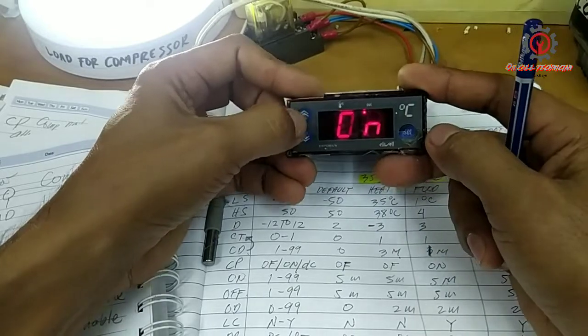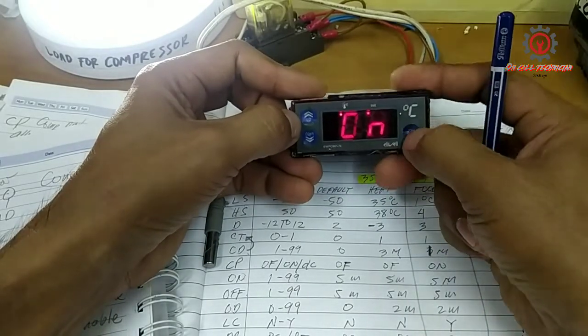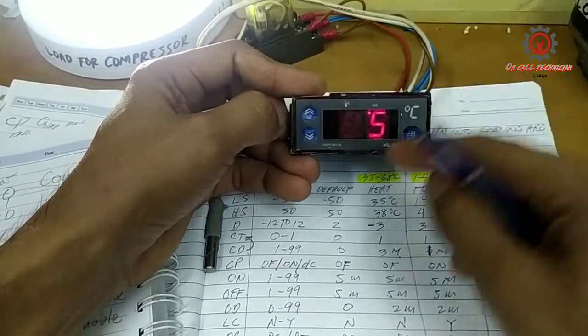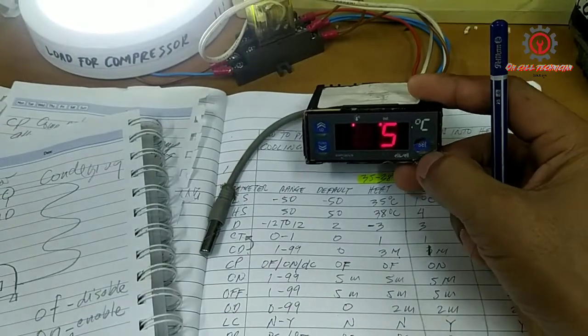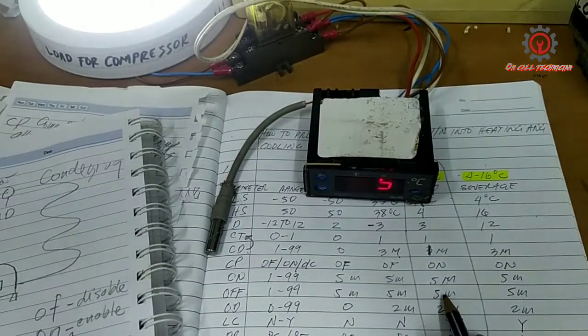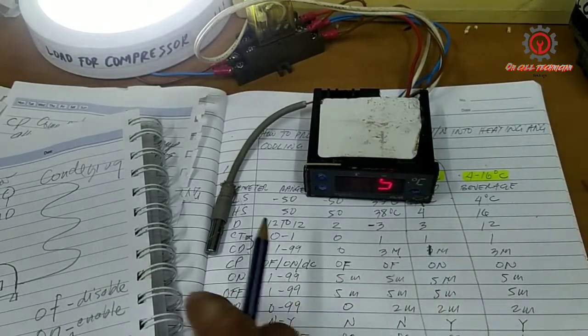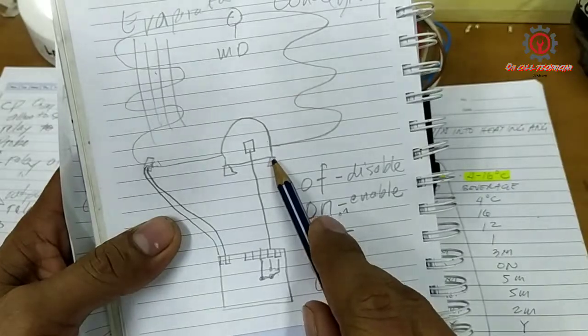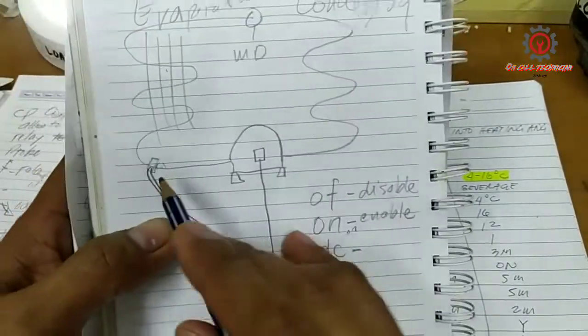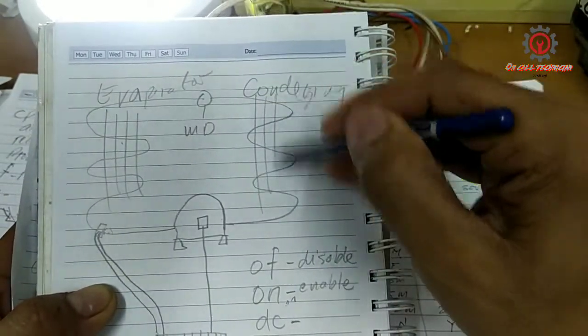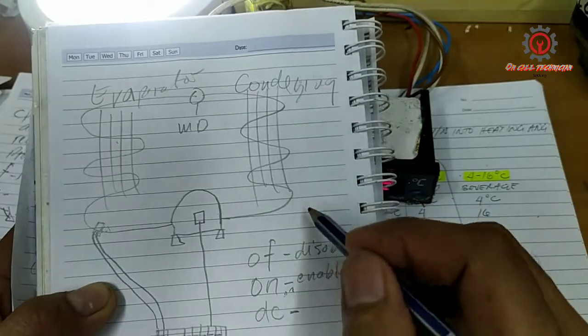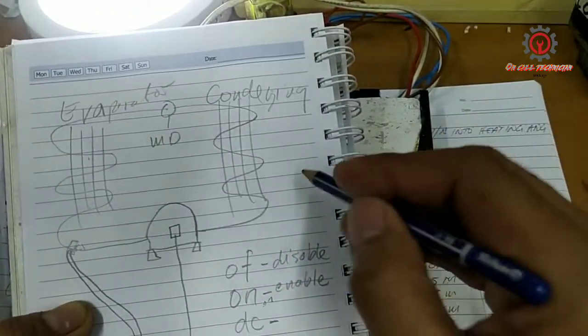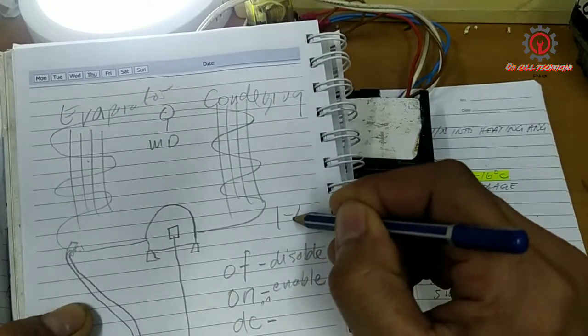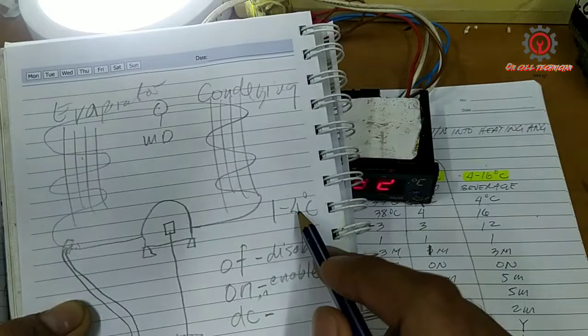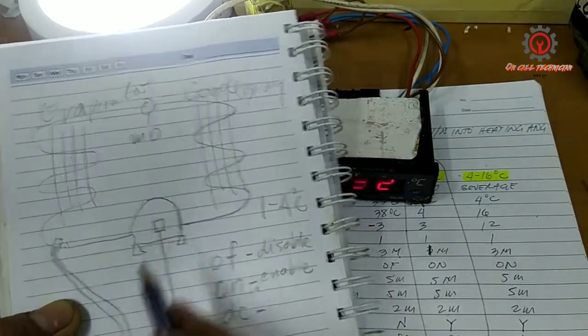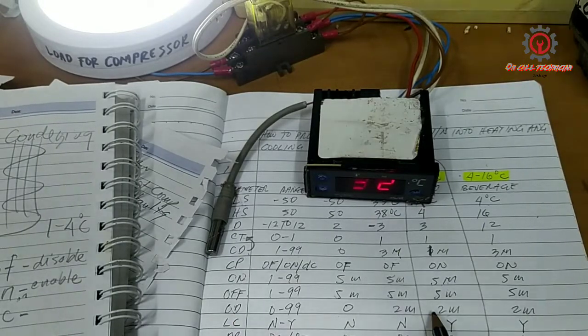Okay, set, and let's go back to on. Okay, done for CP. For on, 5 minutes. Okay, and for the off, 5 minutes. So in case of abnormality, 5 minutes will stop the compressor from running, or just in case the abnormality is in the condenser side, the temperature rises up, and the 1 to 4 degrees Celsius is not in range now, the compressor will stop. Okay, and it will delay with 2 minutes.